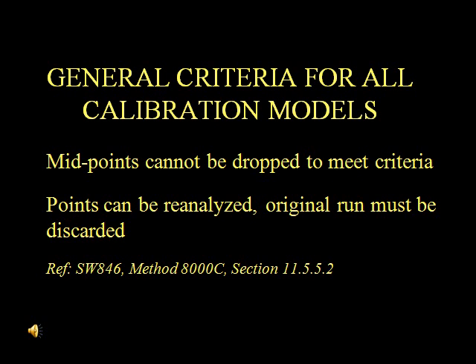The last items we would like to address are some general criteria for all calibration models. These general criteria are used in the determination of an acceptable calibration curve. Midpoints of a calibration curve cannot be dropped just to meet the method criteria or the internal laboratory required criteria.